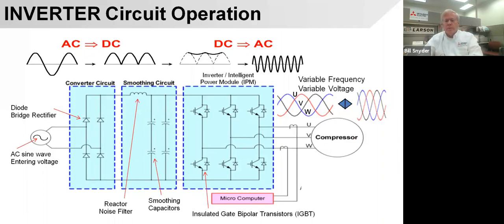It's very, very efficient. These little things here are almost like coils. Think of these as like an amp probe. We're monitoring on the main board what the amps are basically going to that compressor. So we can tell if the compressor is running properly across any two windings, if it's overheating, if it's running high amperage or whatever. We will slow the compressor down, or we will shut it off and throw an error code. We're always trying to protect the equipment.